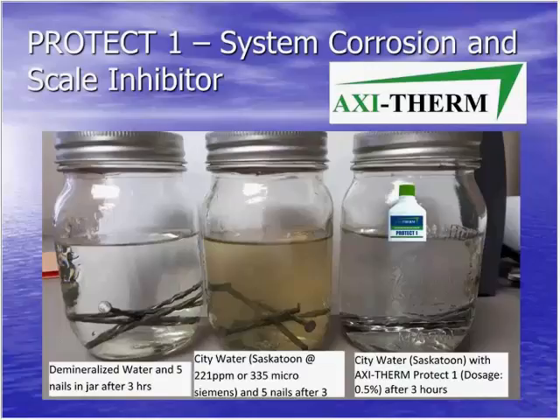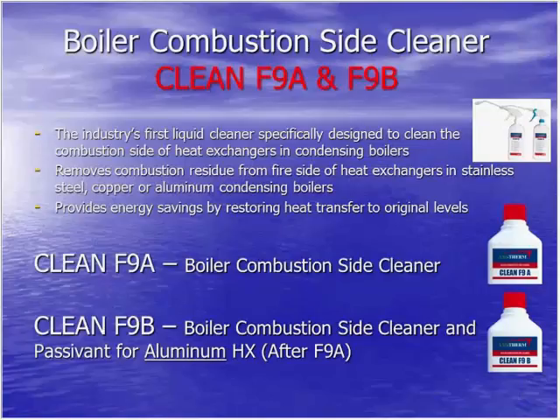And the other product category within system cleaners is our combustion side cleaner. It's actually the industry's first liquid cleaner specifically designed to clean the combustion side of heat exchangers in condensing boilers. And they come in 1 liter bottles with a convenient spray handle with an extension nozzle that allows you to get a better angle on all the nooks and crannies of the inside of a heat exchanger.